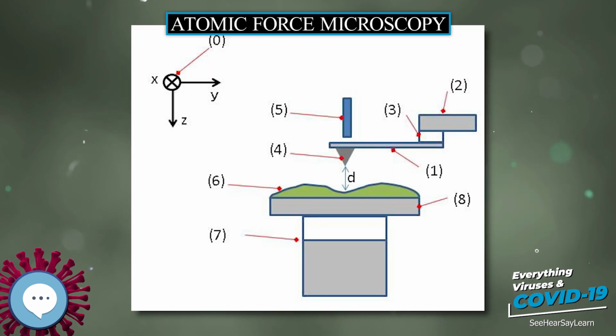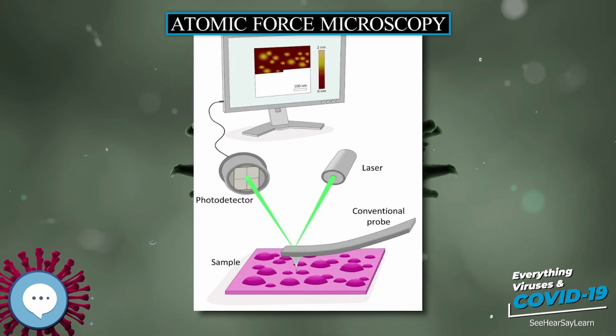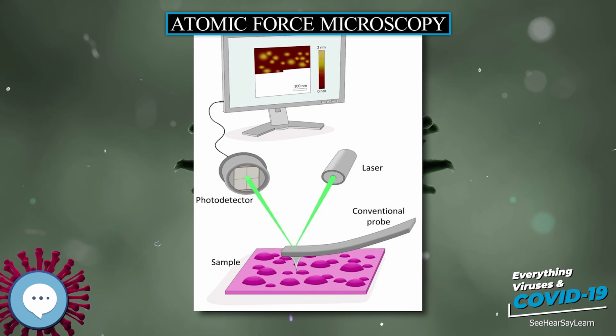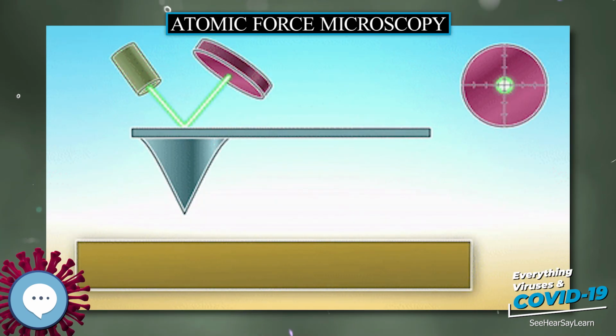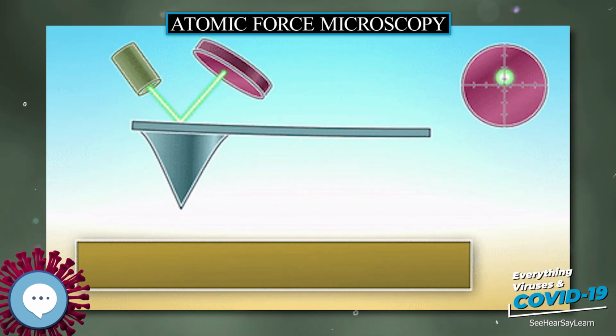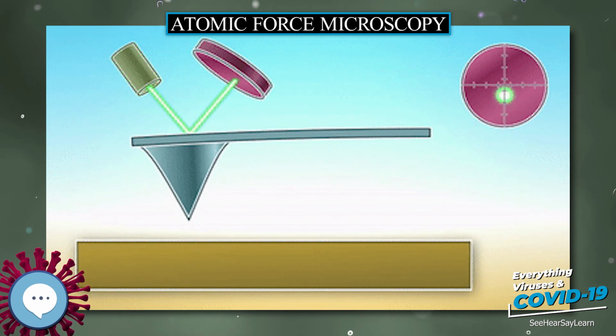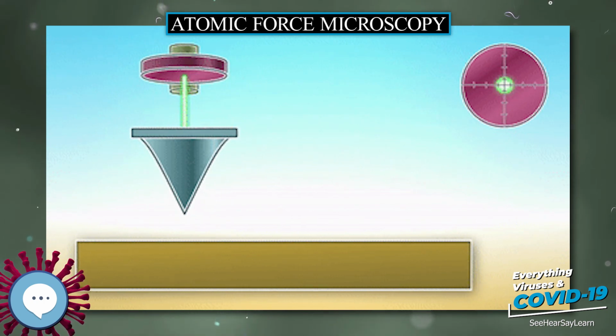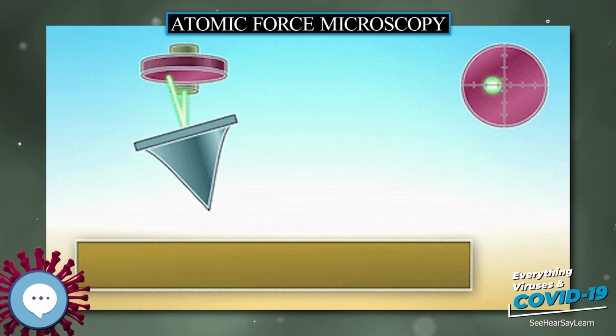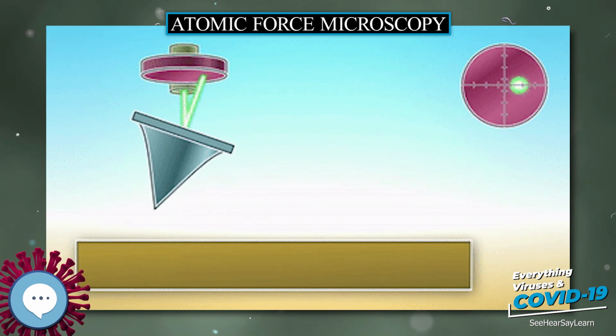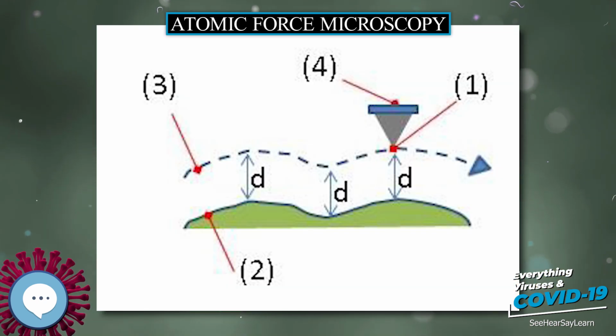Force spectroscopy. Another major application of AFM, besides imaging, is force spectroscopy, the direct measurement of tip-sample interaction forces as a function of the gap between the tip and sample. The result of this measurement is called a force-distance curve. For this method, the AFM tip is extended towards and retracted from the surface as the deflection of the cantilever is monitored as a function of piezoelectric displacement.